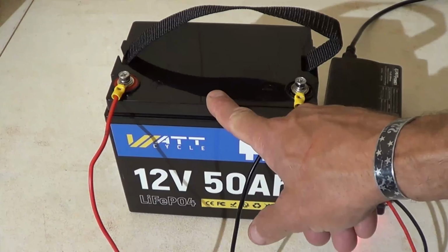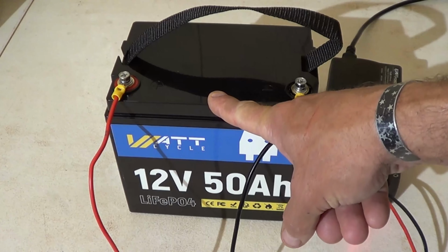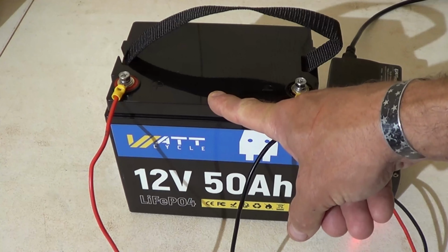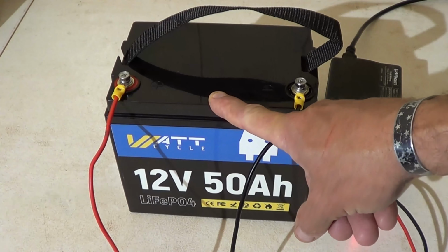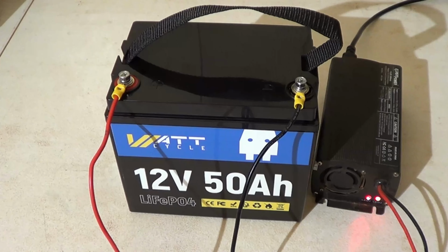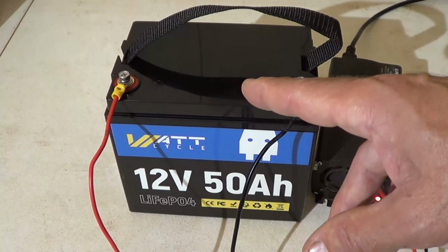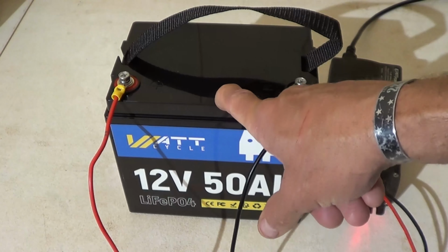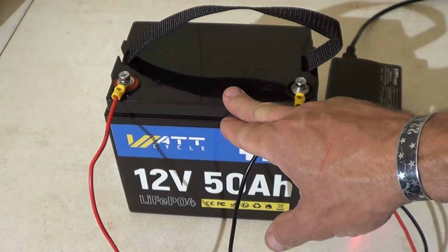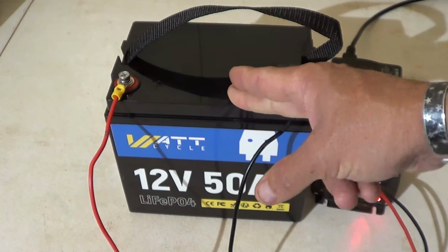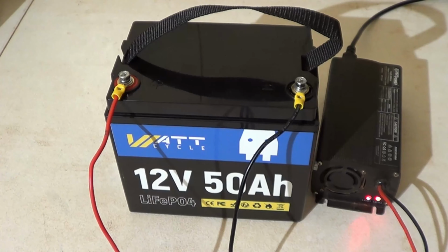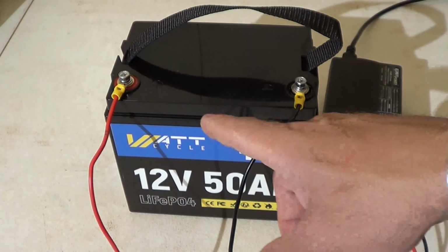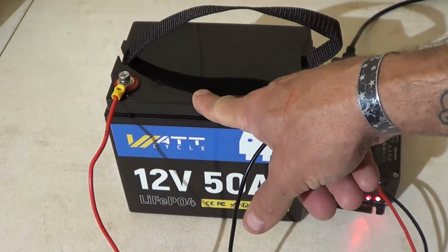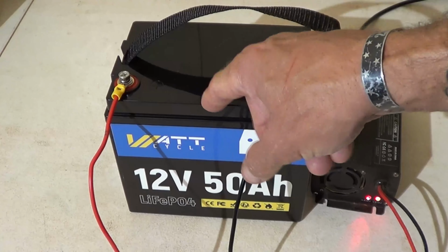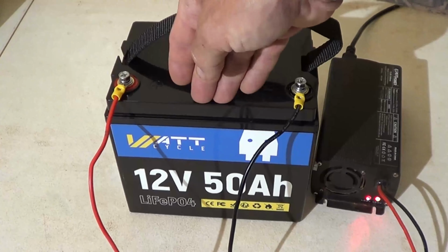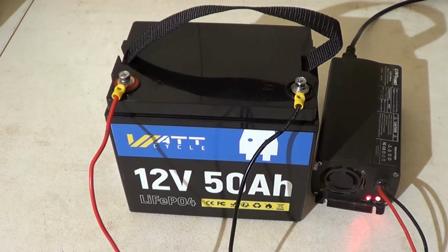Now, charging high temperature protection. The BMS will not allow a charging current if the internal temperature of the battery has reached 149 degrees Fahrenheit or 65 degrees centigrade. When it comes to the discharging high temperature protection of this battery, the BMS will not allow a discharging current if the internal temperature of the battery has reached 158 degrees Fahrenheit or 70 degrees centigrade. Now, low temperature charging and discharging current: the BMS will not allow a charging current under 32 degrees Fahrenheit or 0 degrees centigrade, but it will continue to discharge down to -4 degrees Fahrenheit or -20 degrees centigrade.